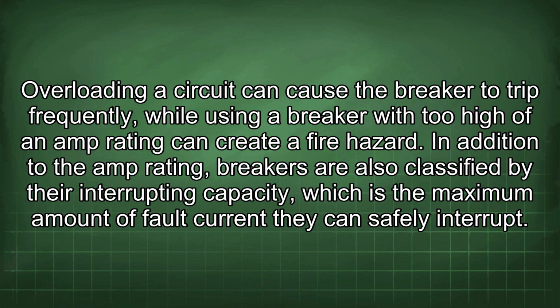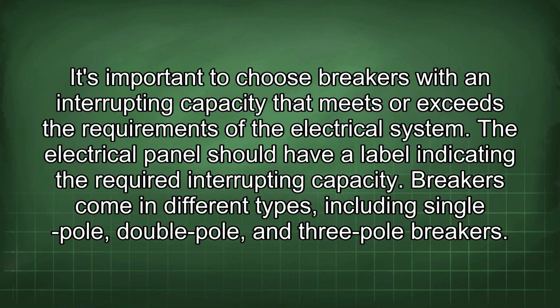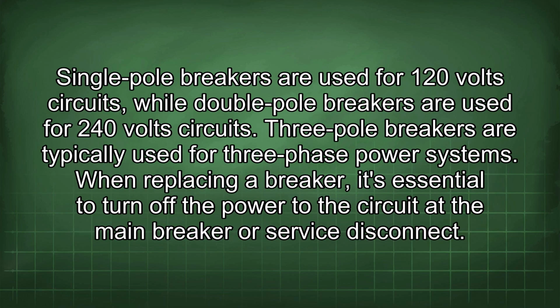In addition to the amp rating, breakers are also classified by their interrupting capacity, which is the maximum amount of fault current they can safely interrupt. It's important to choose breakers with an interrupting capacity that meets or exceeds the requirements of the electrical system. The electrical panel should have a label indicating the required interrupting capacity. Breakers come in different types, including single-pole, double-pole, and three-pole breakers. Single-pole breakers are used for 120-volt circuits, while double-pole breakers are used for 240-volt circuits. Three-pole breakers are typically used for three-phase power systems.